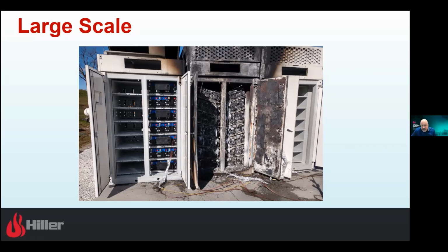What are mitigation measures? If they want a suppression system, that'll work on an electrical fire, but not really on an electrolyte fire. So if we had an inverter or power supply wiring fire and put it out, it wouldn't damage the batteries. So there's a little bit of risk tolerance there.